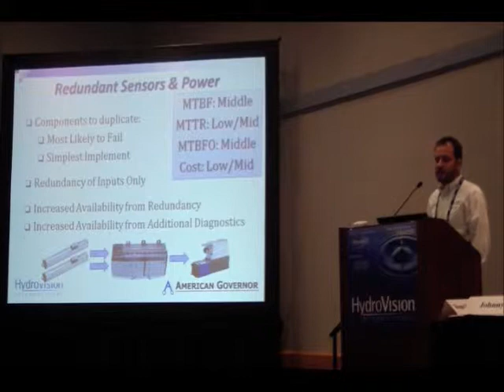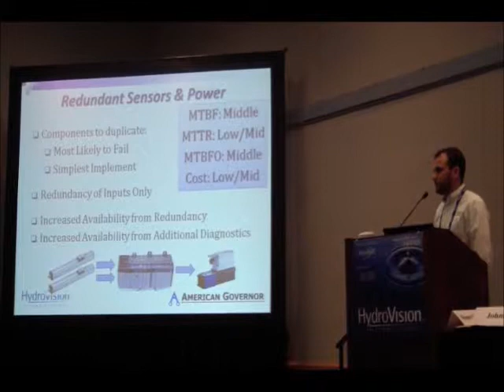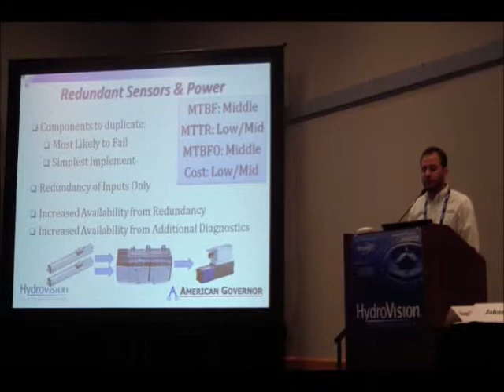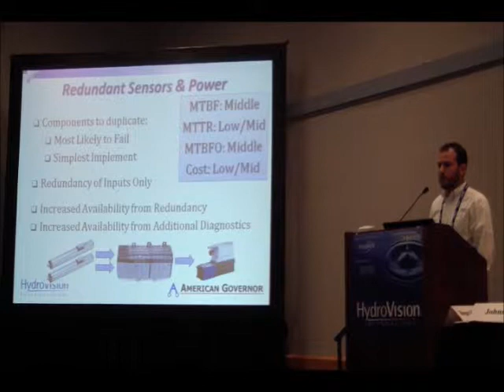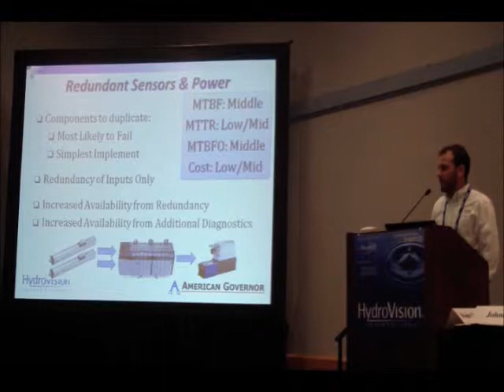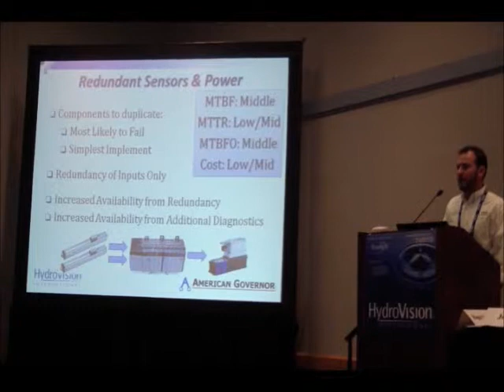And this is because you have increased availability from two sources. Obviously your redundancy. If one power supply fails, swap over to the other one. You keep running. But also increased availability from additional diagnostics. If you have two pressure transducers and they disagree, you know you have a problem. If you only had one and it was off or was miscalibrated, you might not know you have a problem. So there's a whole another level of diagnostics and information that you gain just from simple redundancy.